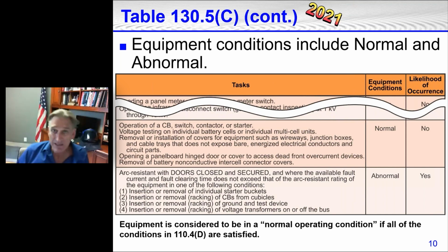And remember, in the last slide, we saw equipment condition any, and now it says equipment condition, we have normal and abnormal. And so we've got like the first one in the normal column, the normal row, operation of a circuit breaker, switch, contactor, or starter. If the equipment is in normal operating condition, likelihood of occurrence is no. That means no arc-rated PPE is required. And so but this is normal operation of equipment. We're going to, another slide here, we're going to talk about what is normal operation of a circuit breaker, switch, contactor, or starter. We're going to look at that.